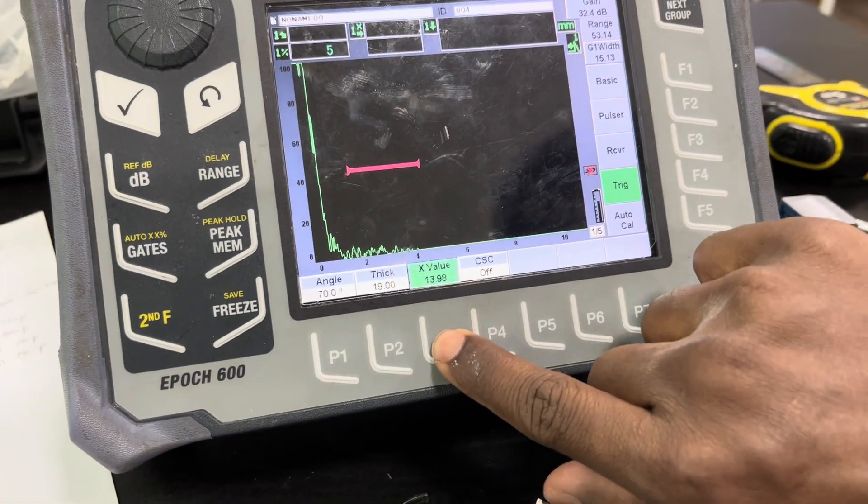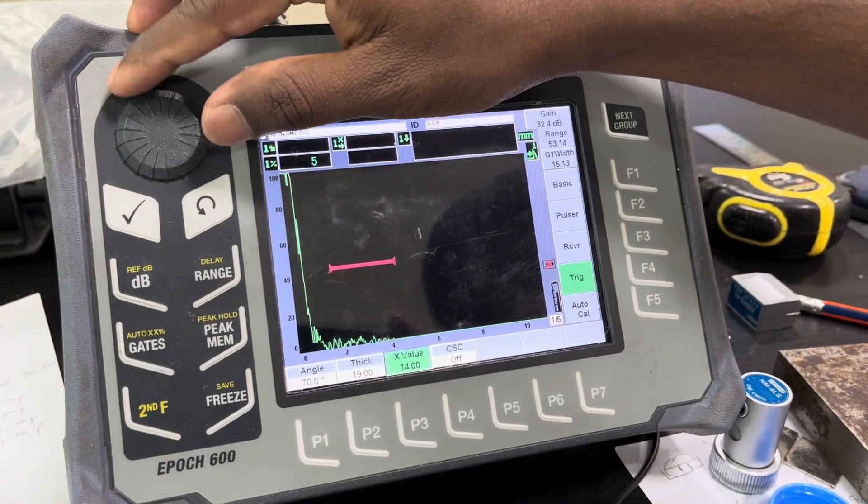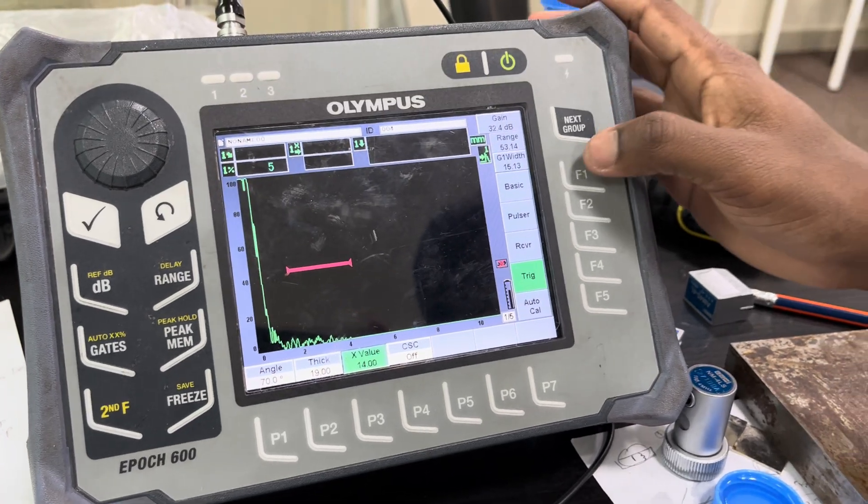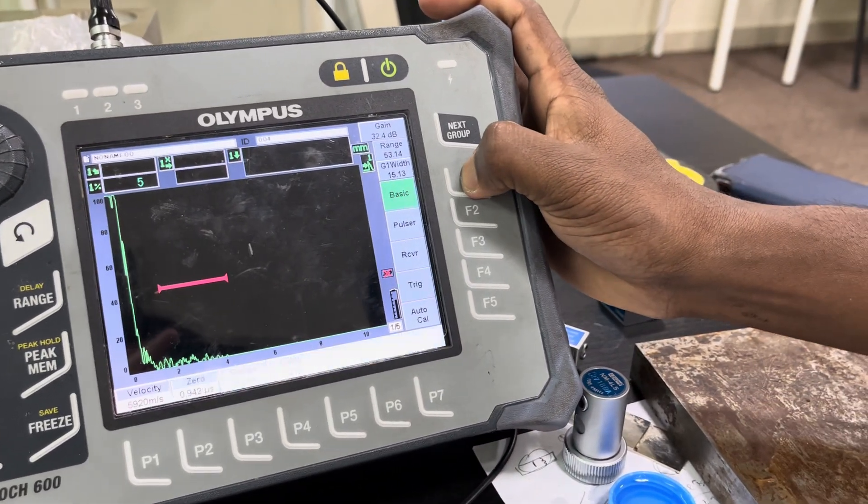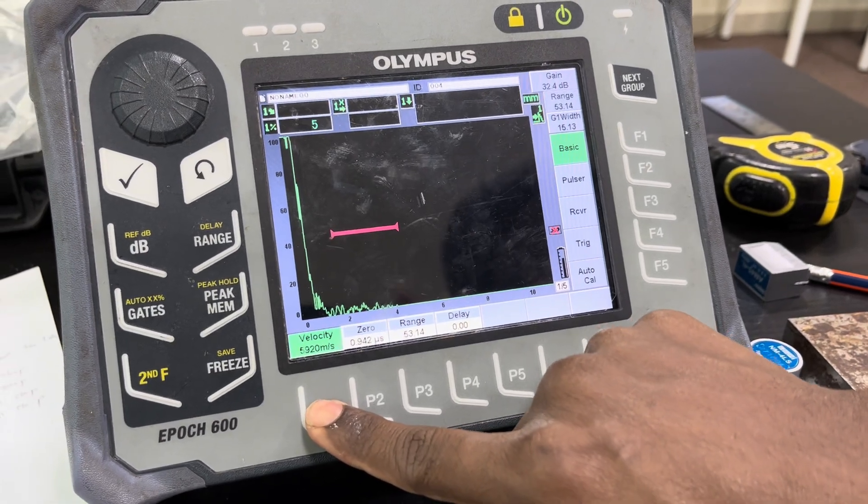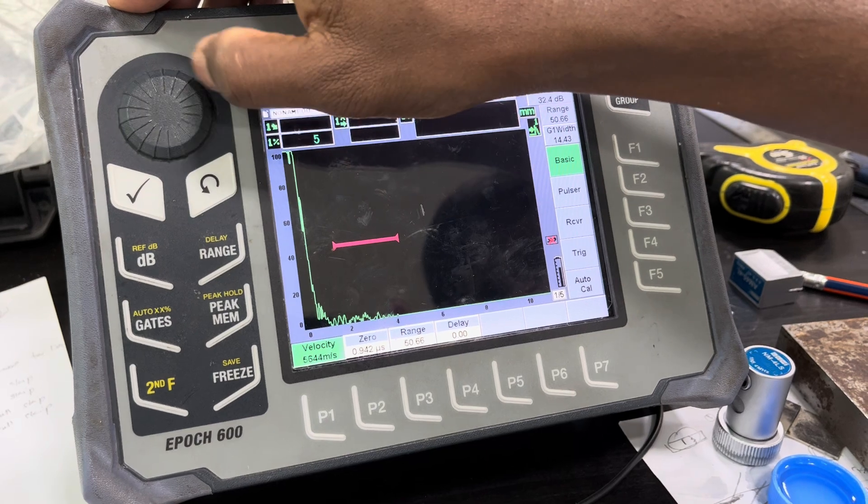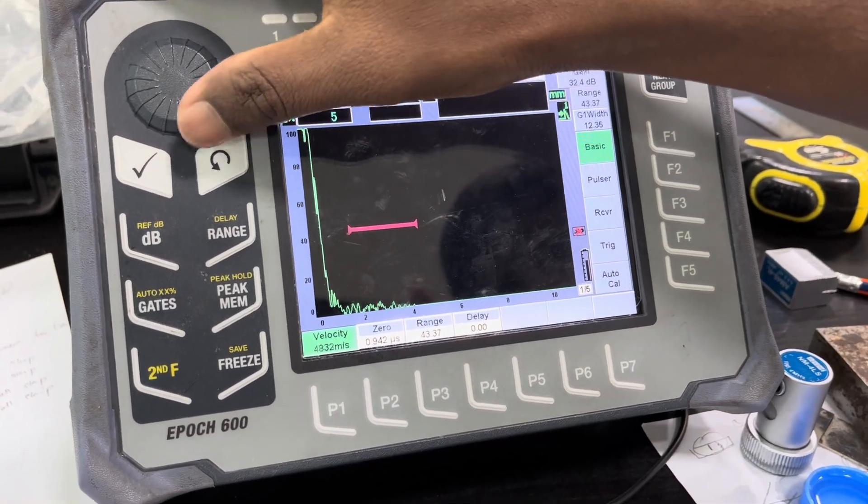When I did the calibration, the X Value was 14. Now I am going to check the velocity of the angle beam. In the machine, the velocity is 3260, so I am going to set 3260.